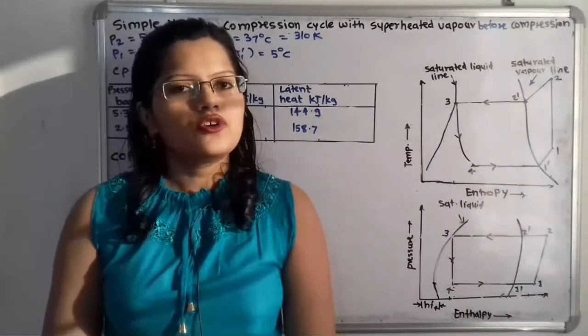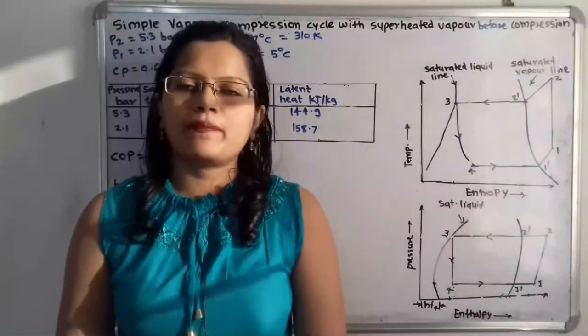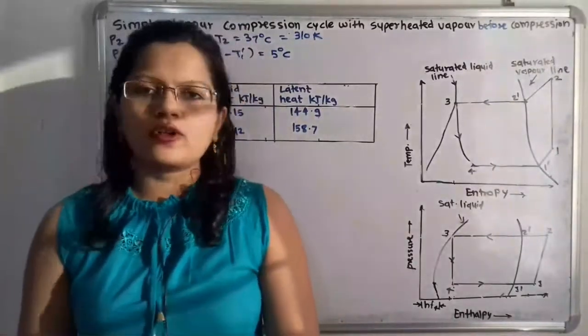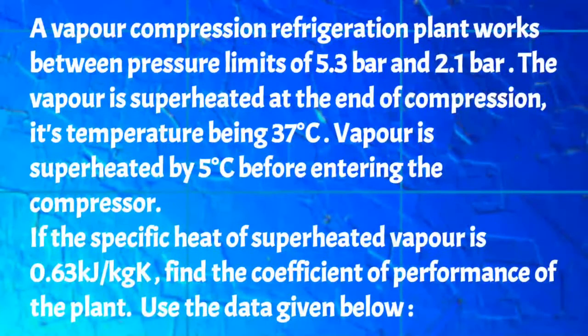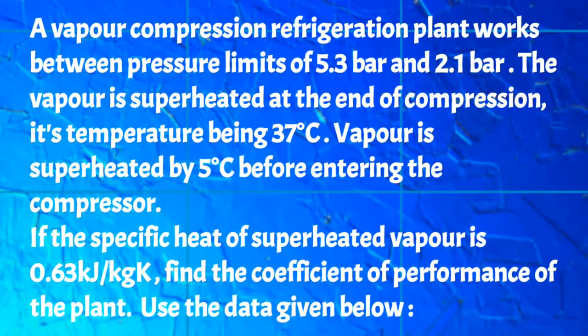Hello friends, this is Priyanka. Today we are going to solve a problem on vapor compression cycle with superheated vapor before compression. A vapor compression refrigeration plant works between pressure limits of 5.3 bar and 2.1 bar. The vapor is superheated at the end of compression, its temperature being 37 degrees Celsius. The vapor is superheated by 5 degrees Celsius before entering the compressor. The specific heat of superheated vapor is 0.63 kJ/kg·K.